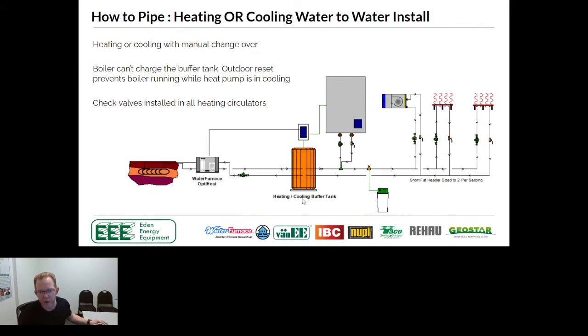So for example, if this was a heating air handler and the air handler is calling, we'll let the air to water or the water to water charge this to 120 degrees. We'll lift it 20 degrees with the boiler to take care of the air handler. The boiler would never come on for the radiant floor unless, for whatever reason, we're in outdoor conditions where maybe it got so cold outside that our 5-ton unit is now a 3-ton unit. We're okay. You know, those 10 really cold degree days, I'm in Ontario, those 10 really cold degree days, this boiler will take care of that and make sure we continue to heat the load.